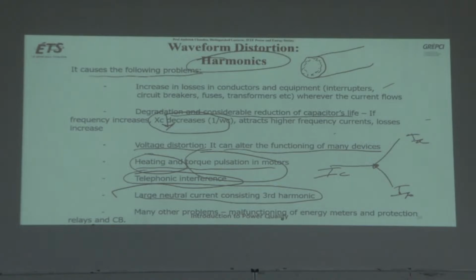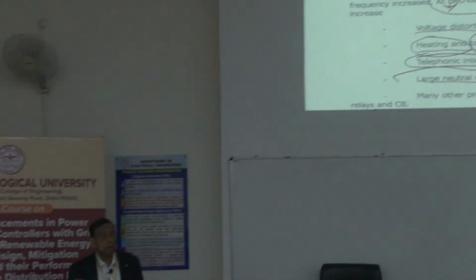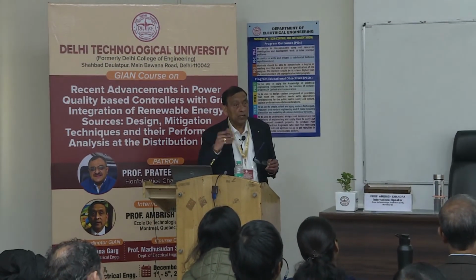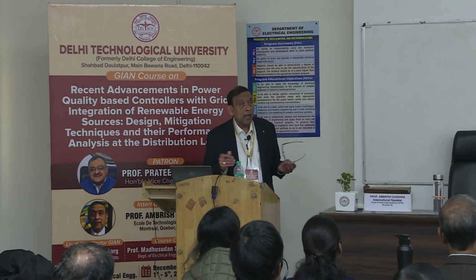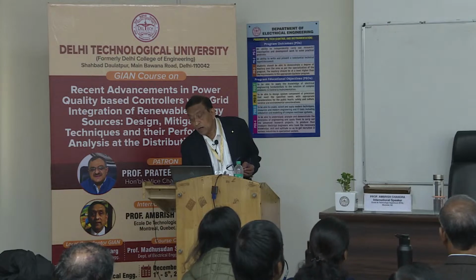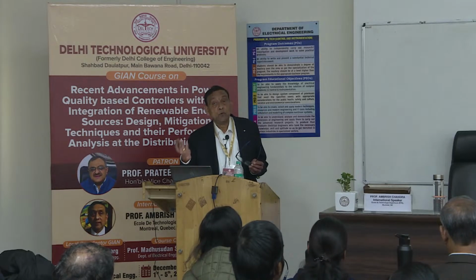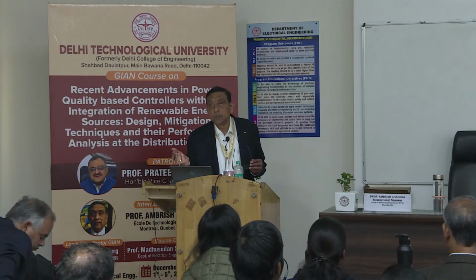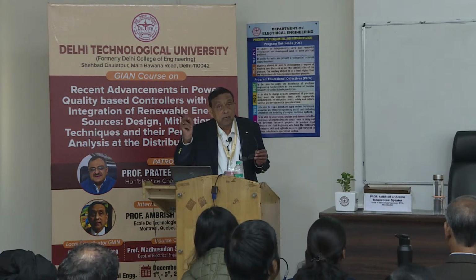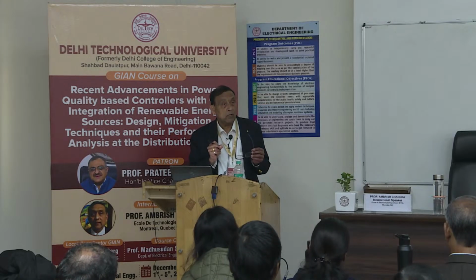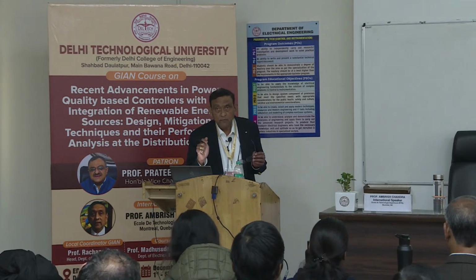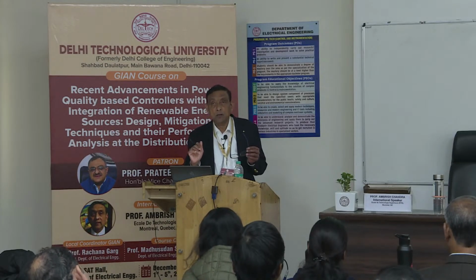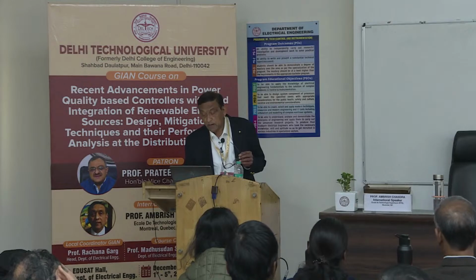So this is what happens if you have a non-linear load. Different harmonics are generated, including the zero sequence harmonics: third, ninth, and 15th, but not sixth, since sixth is an even harmonic. They will add up and finally go to the neutral. That neutral current may be 2 times or 3 times the rated current of the neutral cable you have put, so it may become heated. And if the engineer does not pay attention, it may also burn out. In the worst case, sometimes this happens.